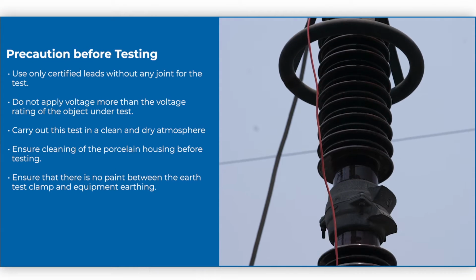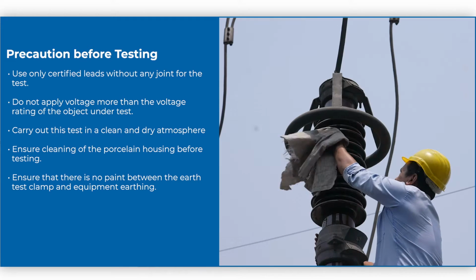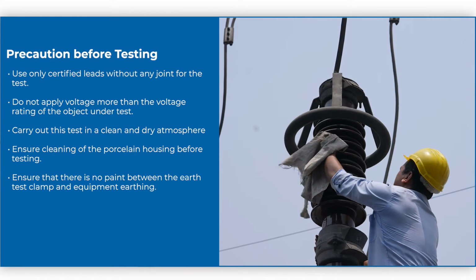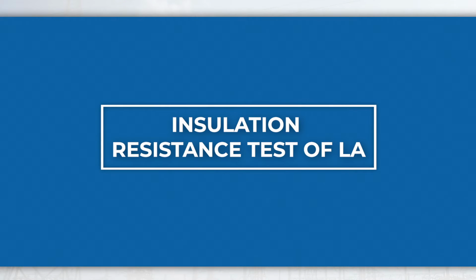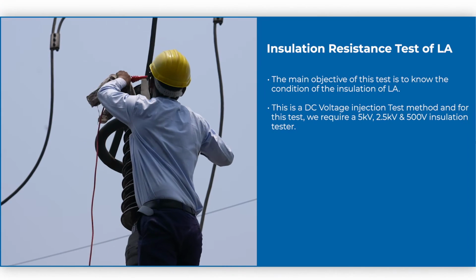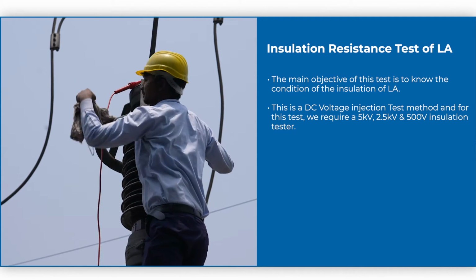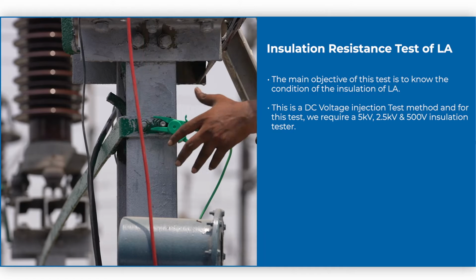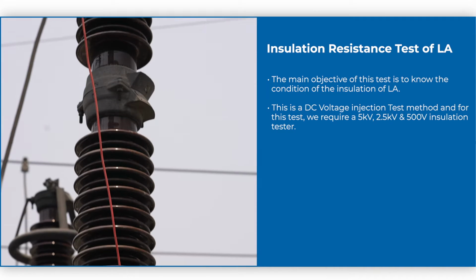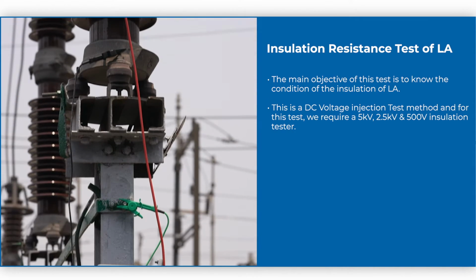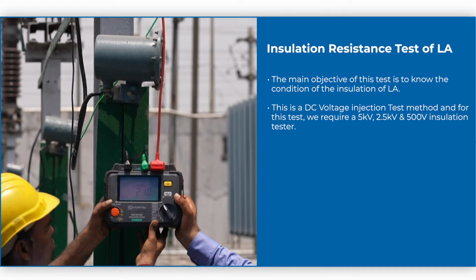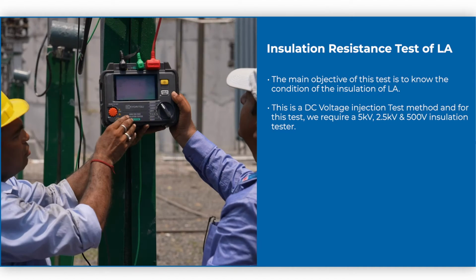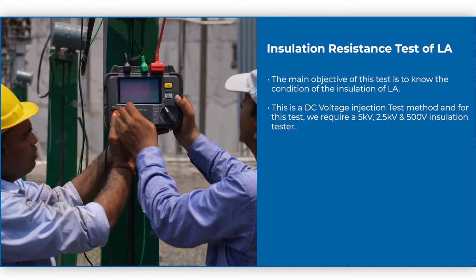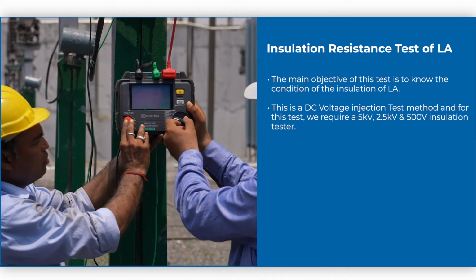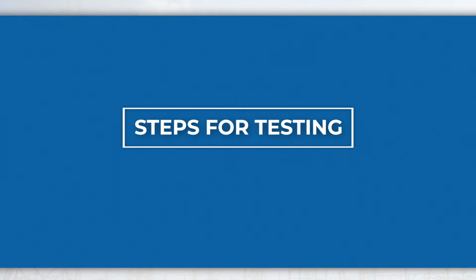Precautions before testing. While performing the tests, these precautions shall be followed. Insulation resistance test of LA. The main objective of this test is to know the condition of the insulation of LA. This is a DC voltage injection test method, and for this test, we require a 5 kV, 2.5 kV and 500 volt insulation tester.